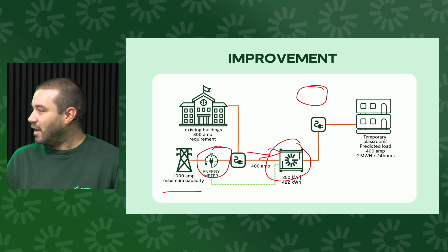Absolutely. So just looking at the results here, the backup generator was needed for around 4% of the energy production over the 18-month period. But from the data that we gathered, we were actually saving around 20,000 litres of diesel per month, based on a comparison with a 500 kVA generator running 24/7. So, of course, diesel saved also means emissions saved. And on a school, you don't want polluting, noisy, so silent running was another thing.